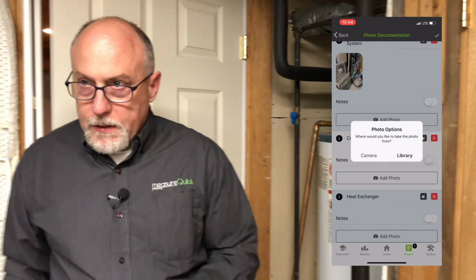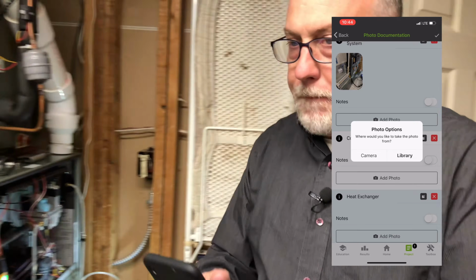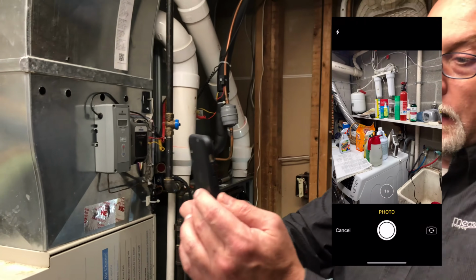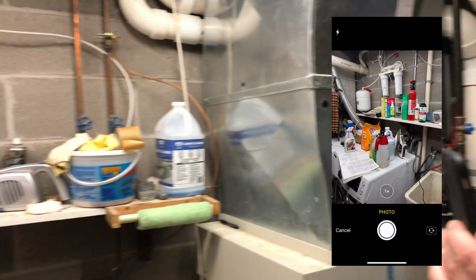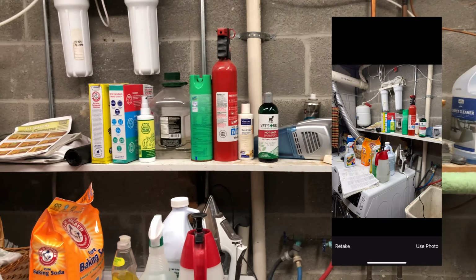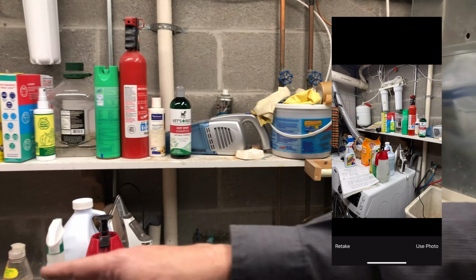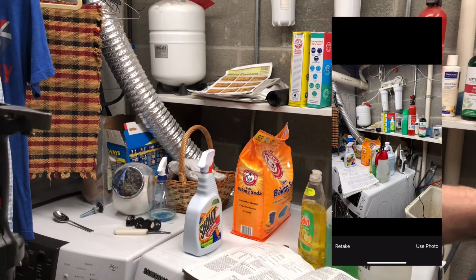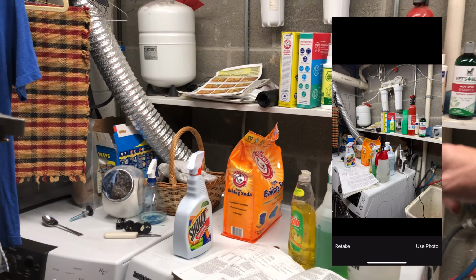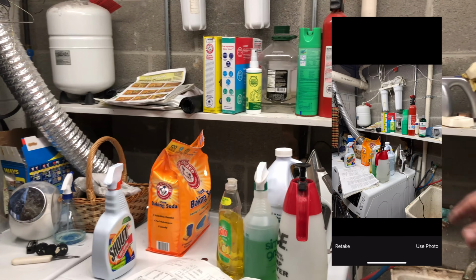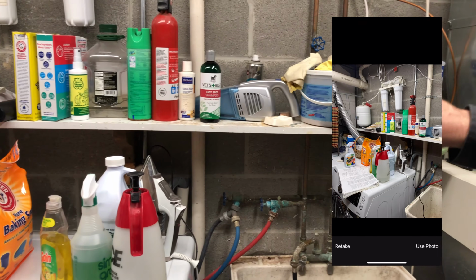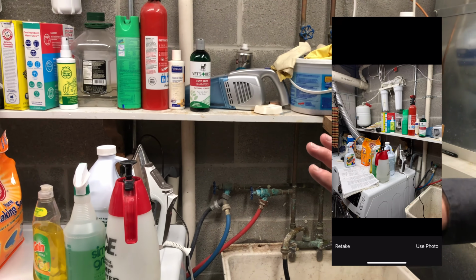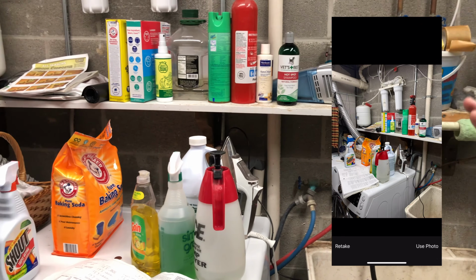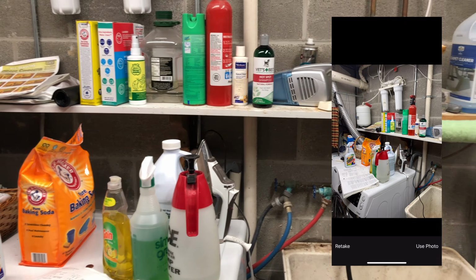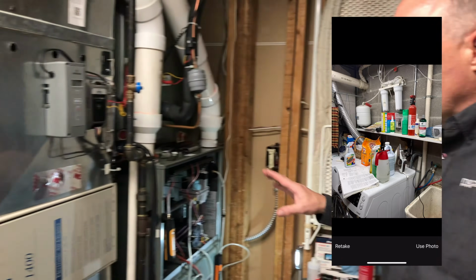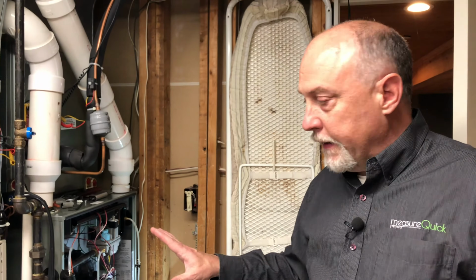So the other thing we want to do here, and here's a big pet peeve of mine, and it's even in my own house, is chemicals near the combustion air zone. Now, my wife keeps most of this stuff closed up. You can see we have our detergent inside of a jar there. She keeps it closed. The Ziploc bags are closed. All these things are capped. But the washer and dryer are very common in these types of areas, and you don't want these chemicals to get pulled into your furnace because they will wreak havoc on making the heat exchanger rot out early.